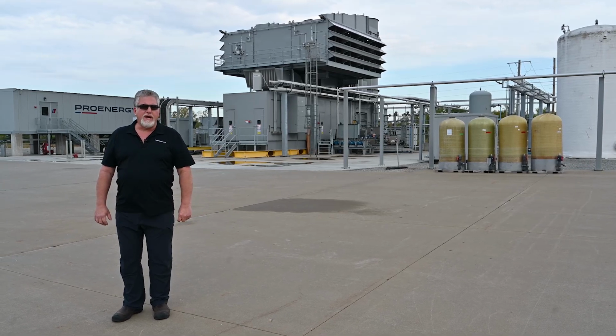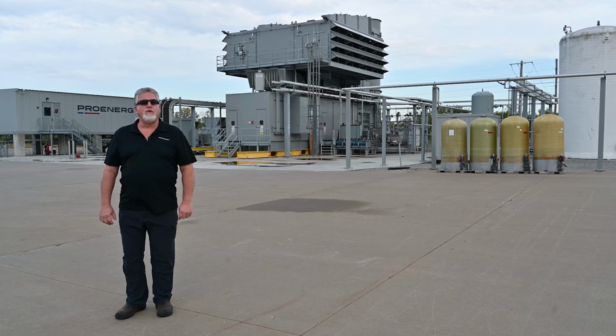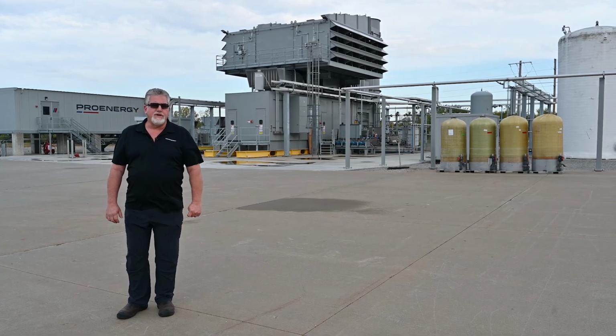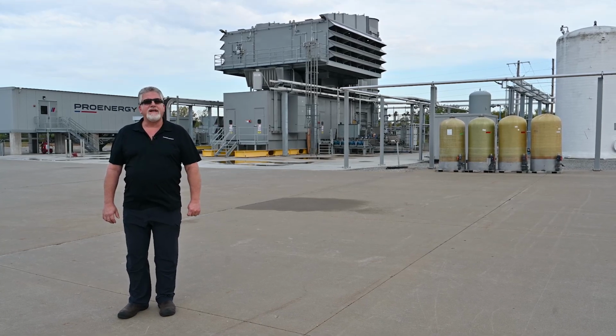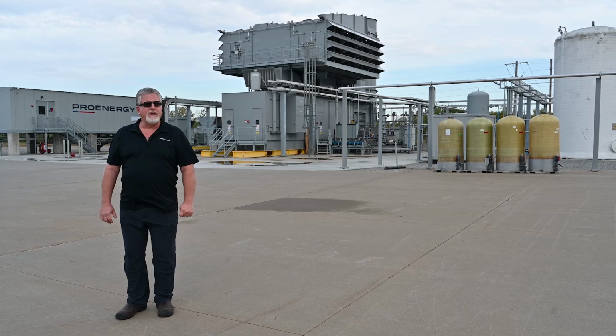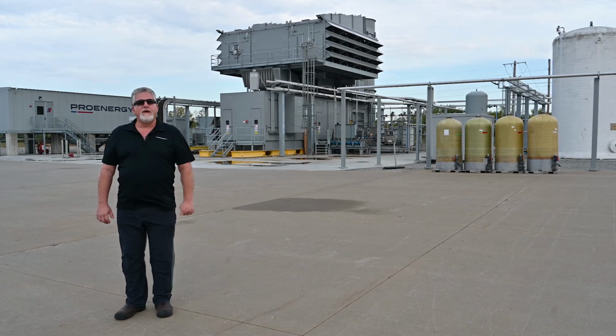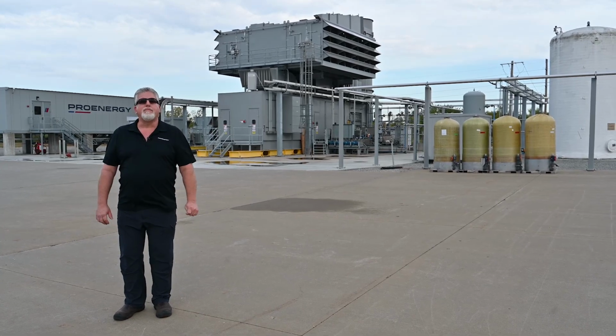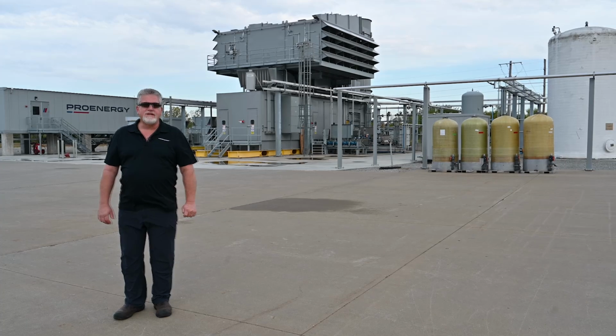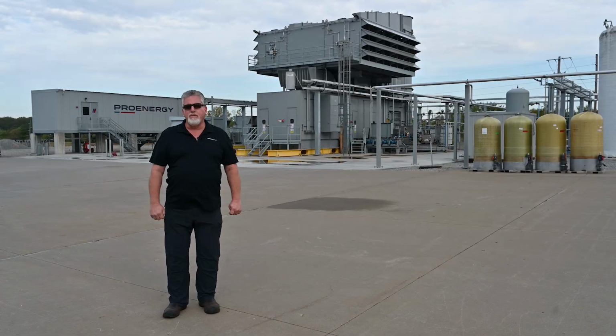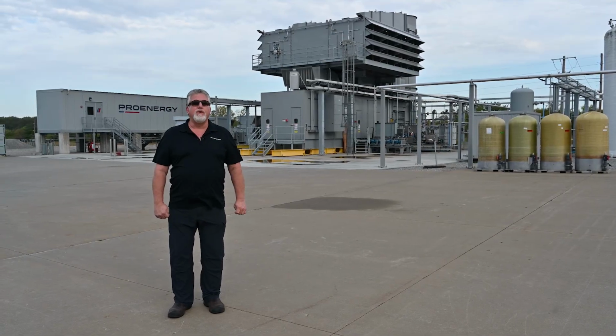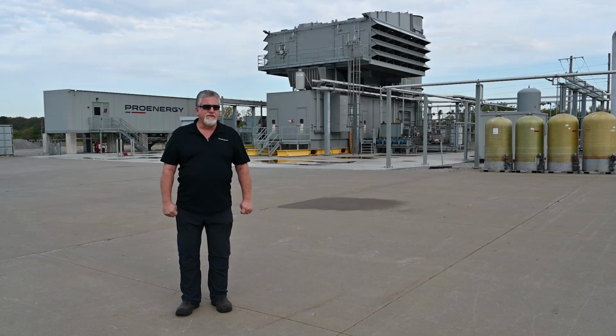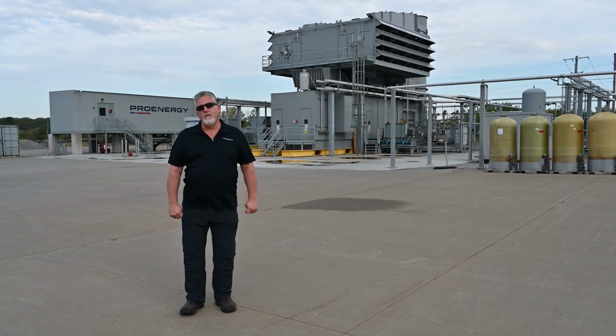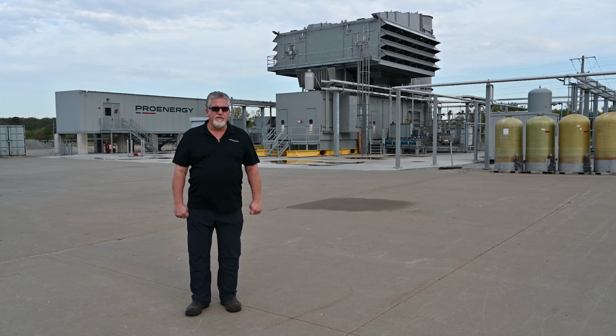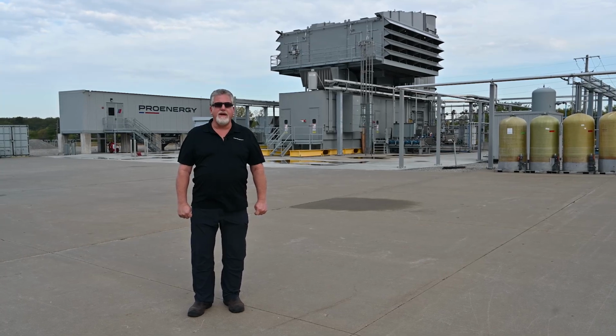If we were on the grid, it's harder to hold that engine for a period of time as the power is needed. Being off the grid and using the load bank allows us more opportunity to test multiple points than on the grid. The grid typically does not like fluctuations that we would have as we're testing the engine, so this gives us full reign to do what we wish when we need to.